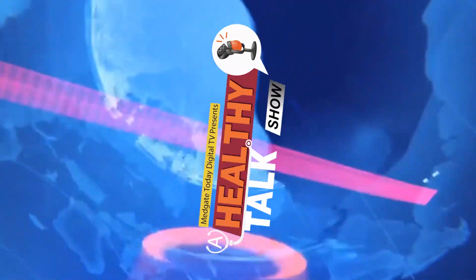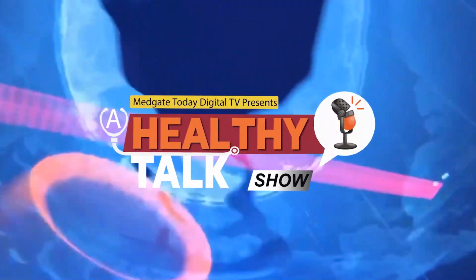Weight bearing MRI sometimes takes some time to acquire the images, 30 to 40 minutes. What will artificial intelligence provide? We will probably acquire the images in 10 minutes, with artificial intelligence performing the additional work that used to take so much time. So this is for sure the next step, to include artificial intelligence in weight bearing MRI.